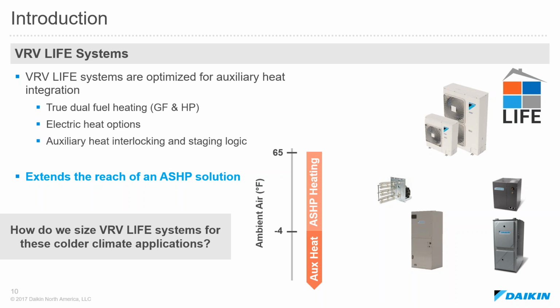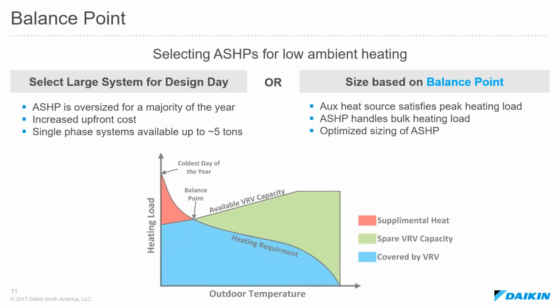So how do we size the system now that we have these two sources coming together? How do we know when to switch over? Traditionally, if you just had an air source heat pump system, you'd select it based off of that design day temperature. So it would always have to meet that design day temperature, so it's going to be large. It's going to be larger than it would be if you were sizing based off of, say, a balance point. So that introduces this balance point curve that I want to talk about.